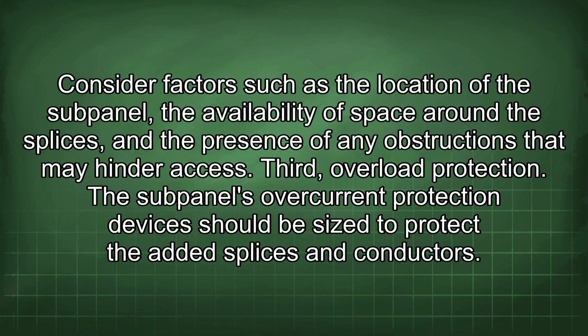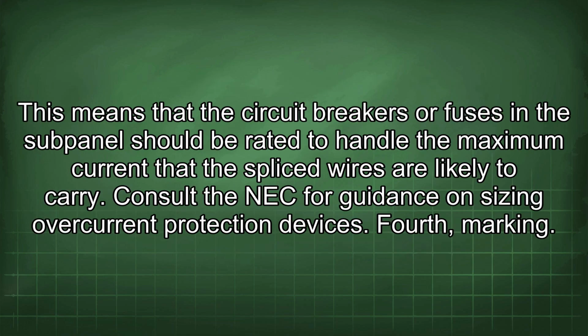Third, overload protection. The subpanel's overcurrent protection devices should be sized to protect the added splices and conductors. This means that the circuit breakers or fuses in the subpanel should be rated to handle the maximum current that the spliced wires are likely to carry. Consult the NEC for guidance on sizing overcurrent protection devices.